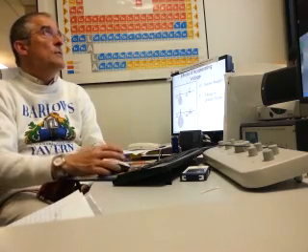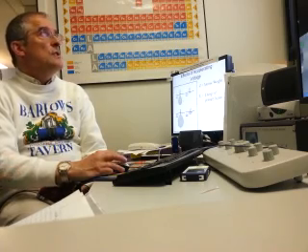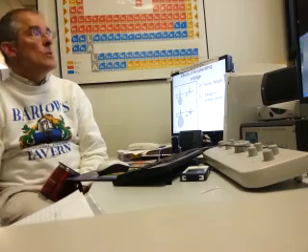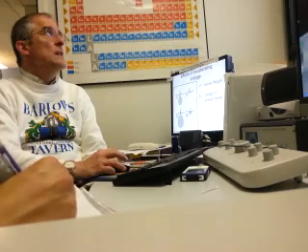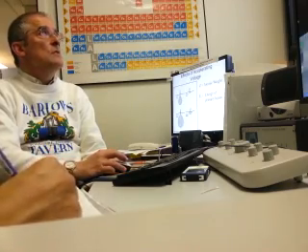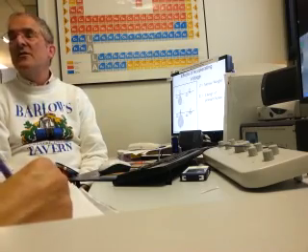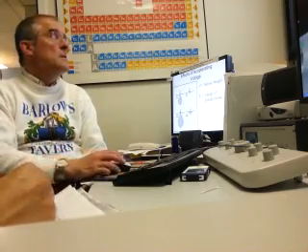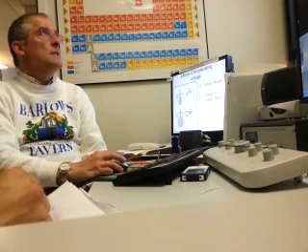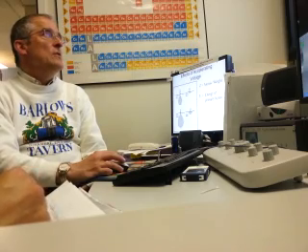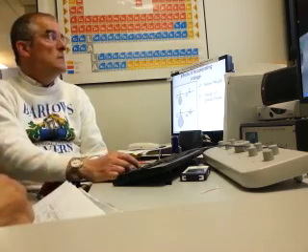All right, so this is the effect of elements. This is low Z and high Z. Those would be atomic weights. As you go from a light element here to a heavy element here for the same accelerating voltage, the Monte Carlo gets a lot smaller because there's not as much power to drive into that heavier metal or material. At low Z and high accelerating voltage, it's going to penetrate deeply, but as the element gets heavier, the Monte Carlo gets smaller.